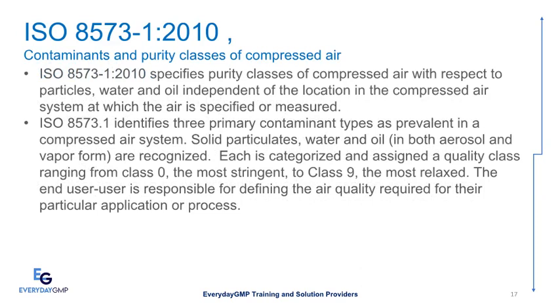ISO 8573-1-2010: Contaminants and Purity Classes of Compressed Air. ISO 8573-1-2010 specifies purity classes of compressed air with respect to particles, water, and oil, independent of the location in the compressed air system at which the air is specified or measured. ISO 8573.1 identifies three primary contaminant types prevalent in a compressed air system: solid particulates, water, and oil, in both aerosol and vapor form. Each is categorized and assigned a quality class ranging from Class 0, the most stringent, to Class 9, the most relaxed. The end-user is responsible for defining the air quality required for the particular application or process.